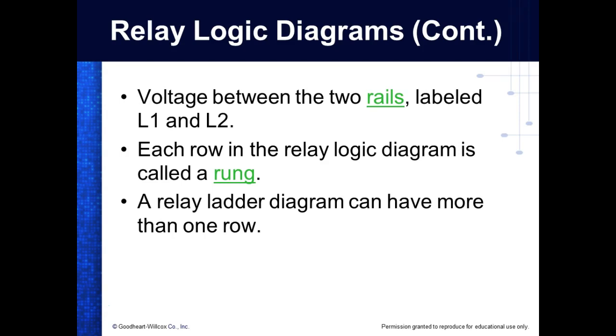What happens all the time is people want to use that 208 volt label for L1. So in motor controls we started calling our control rails CL1 and CL2. We specified that the L1 at 208 volts is not the same L1 as on your control circuit. So when they say they're labeled L1 and L2, it's probably going to be something a bit different, but usually L1 and L2 is part of the name - it usually ends with that.